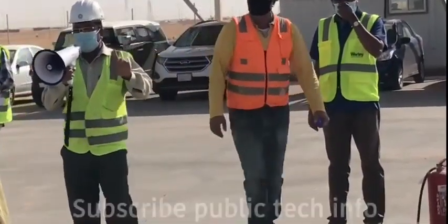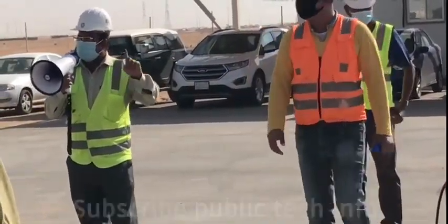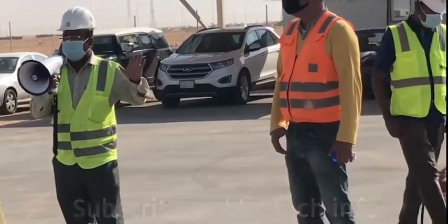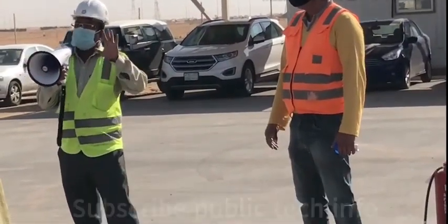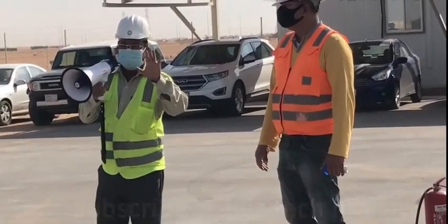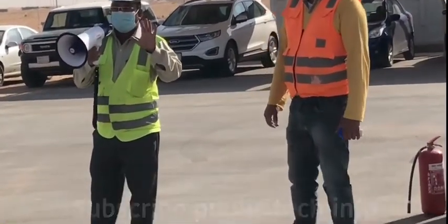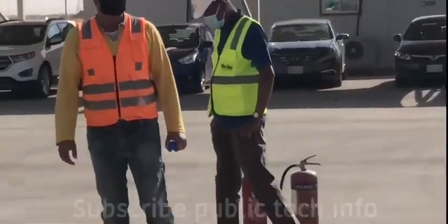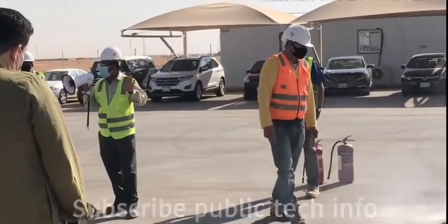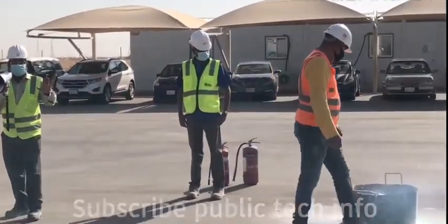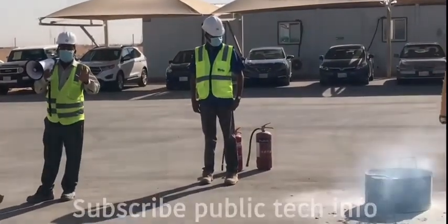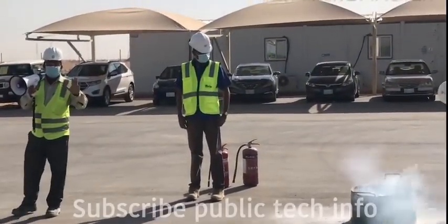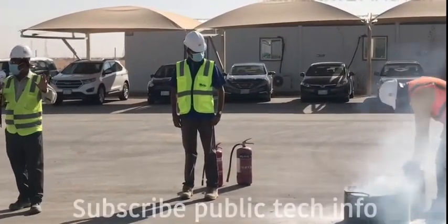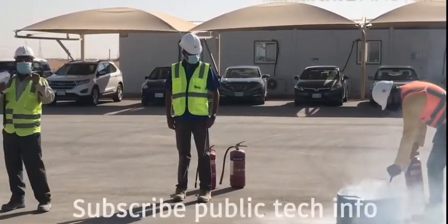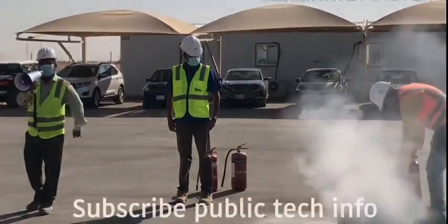Fire extinguisher A is for ordinary fire like paper, wood, or similar. B stands for gases, grease, oil. C is for electrical, using the CO2 fire extinguisher, carbon dioxide. D is for metallic fires, like sodium and magnesium. And K stands for kitchen; for kitchen fires we use the K fire extinguisher.